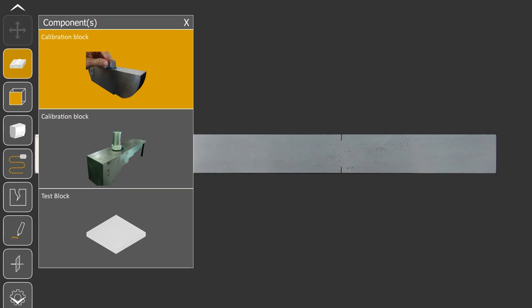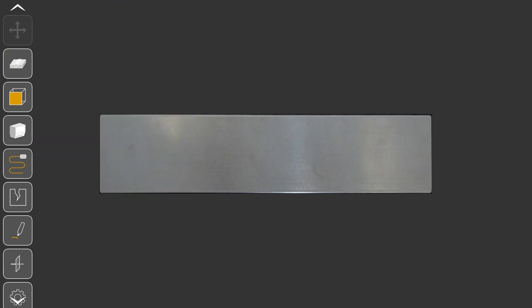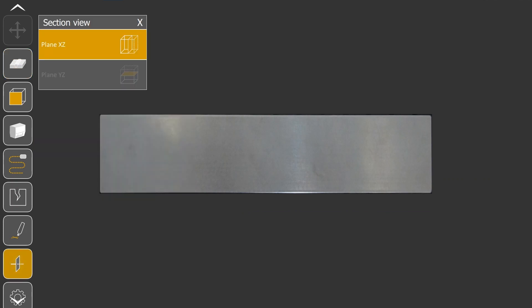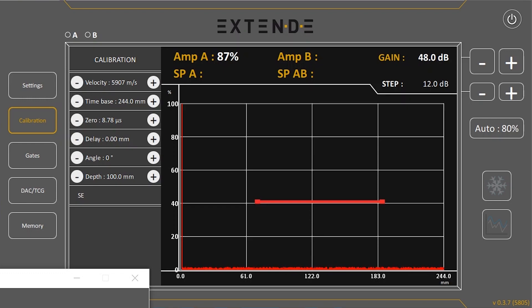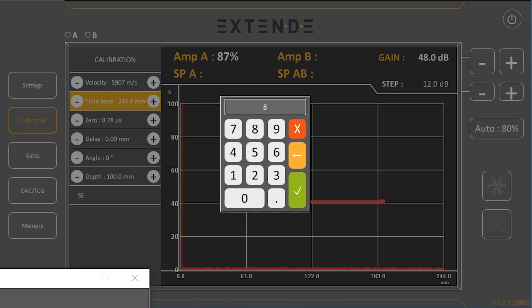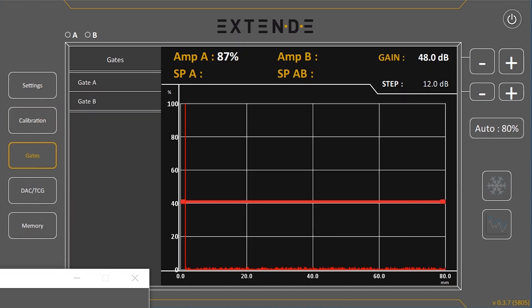Let's switch the component to the step block in order to create the sensitivity curve of the probe. Reopening the section view will help you locate your dummy probe on the block. The step block has a maximum depth of 60 mm, so let's change the time base to 80 mm and change gate A to fit the screen width.